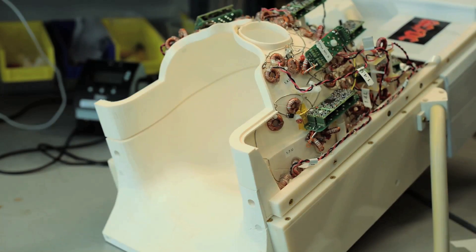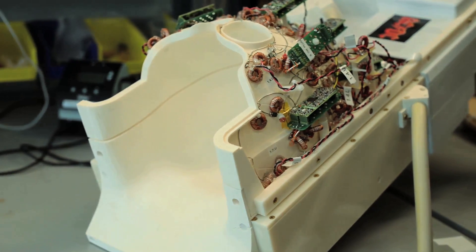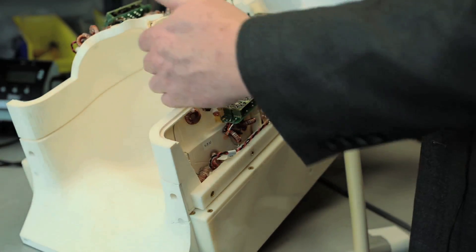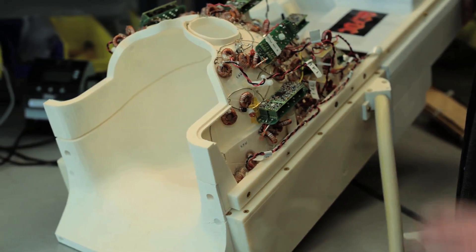This is an example of one of the new class of MRI detectors we've developed for imaging the human brain. It uses multiple detectors placed all over a very close-fitting helmet to detect the signal more sensitively and also to help figure out where the signal came from.